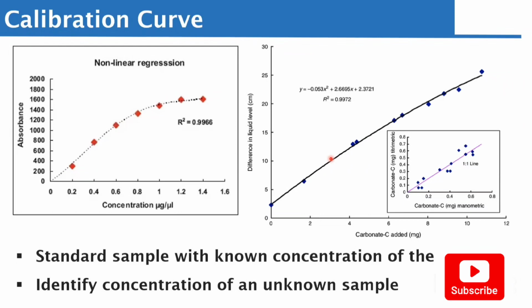Now, what exactly am I trying to talk about here? I'm trying to say that when you are performing a calibration, what you are generating is a curve. And that curve is the target range in which the analyzer is going to measure. Anything outside that target range, the analyzer cannot measure.